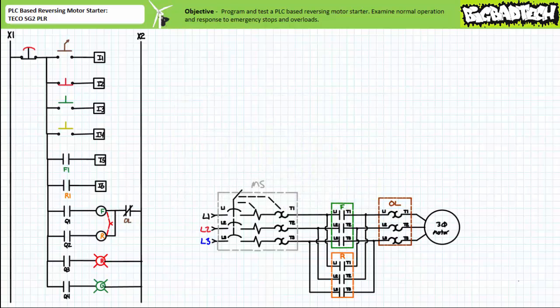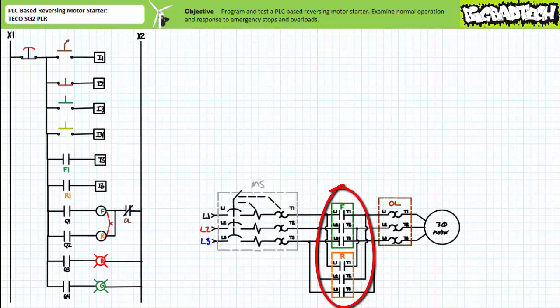This aforementioned lecture configured a TECO SG2 PLR, an inexpensive basic PLC, to direct the operation of light industrial, 120 volts line to neutral, 208 volts line to line, 60 hertz, three-phase AC primary circuit, configured such that the F contactor energizes a squirrel cage induction motor in the forward direction and the R contactor energizes it in the reverse direction. The F and R contactors are mechanically interlocked such that they cannot be simultaneously closed.